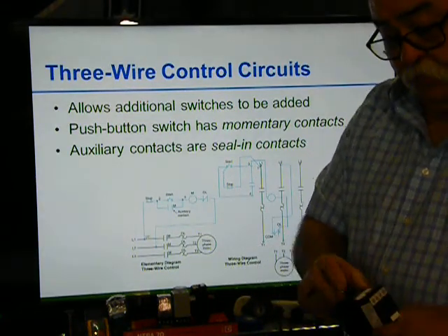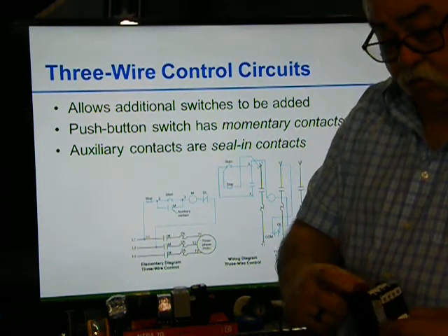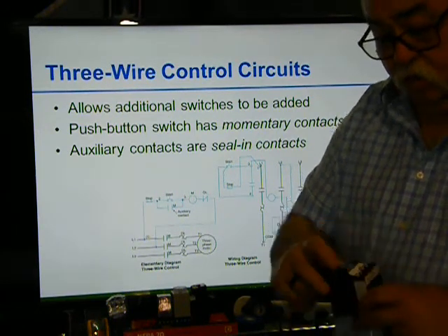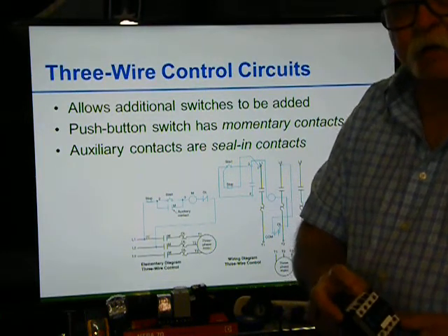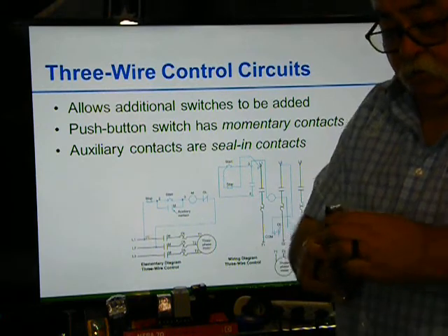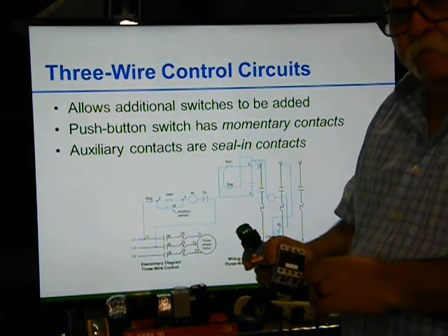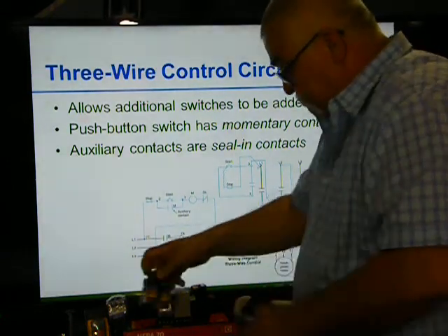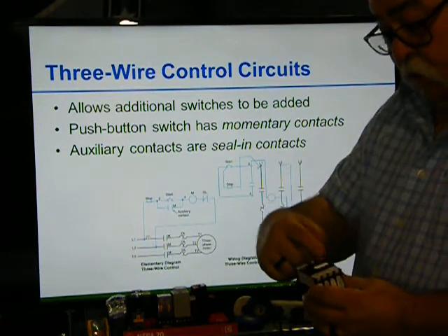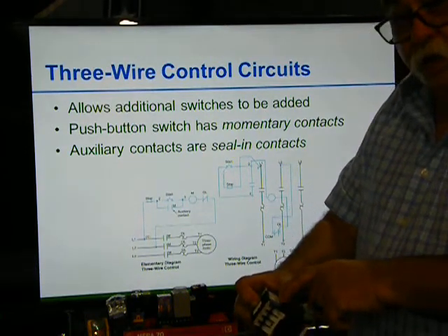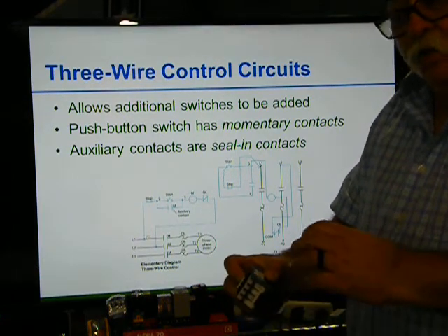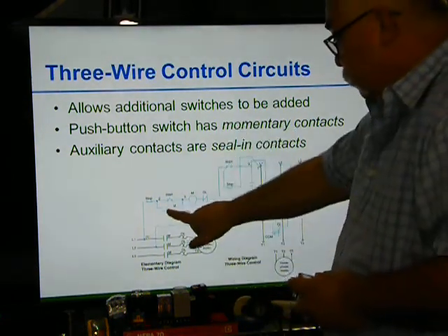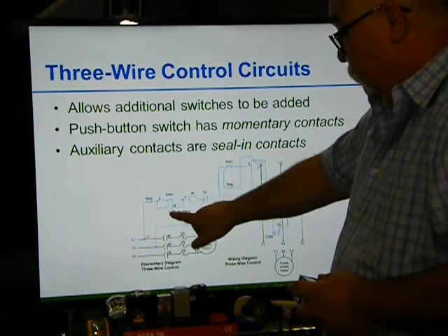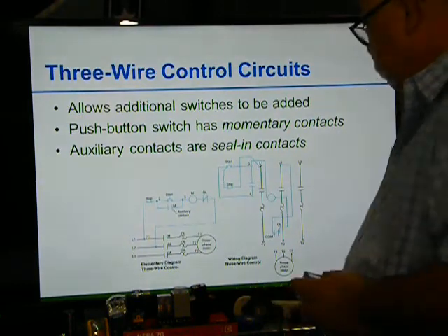So off the 4, my coil is down here. This is 120 volt. So my neutral would be A1, and off the 4, I come down here. I'm also going to go from the number 4 here to the number 4 here. And that's how it gets hot. So what happens is when you push the start button, it sends power, this closes that auxiliary contact, that sealed contact that's in here. There's electricity, boom, and it closes. So this is always closed, and this goes from being open to being closed.